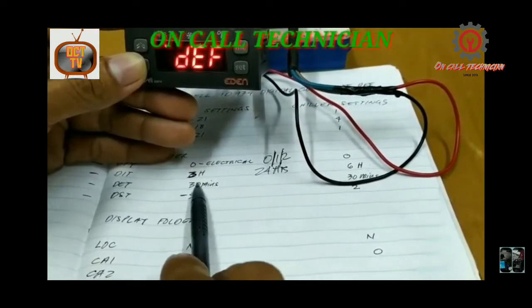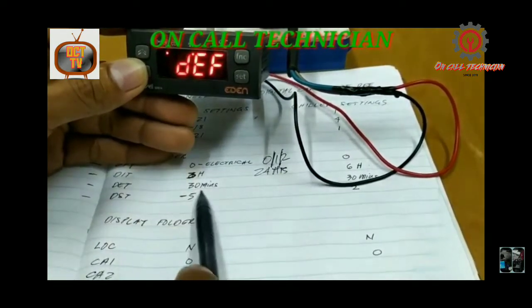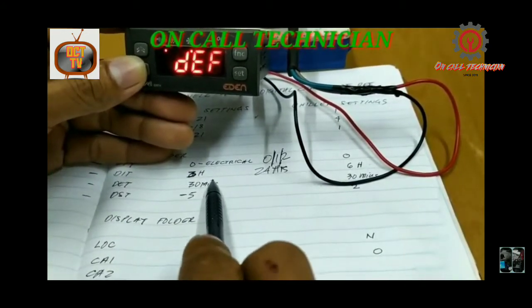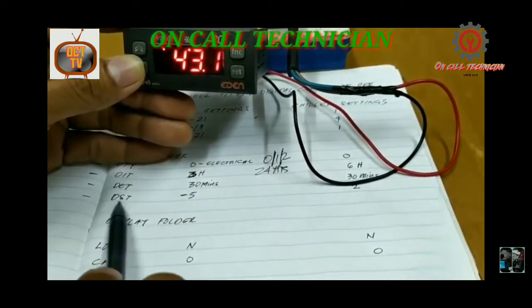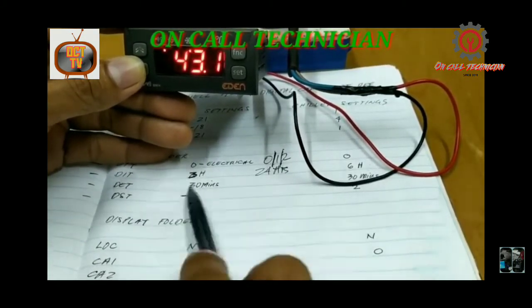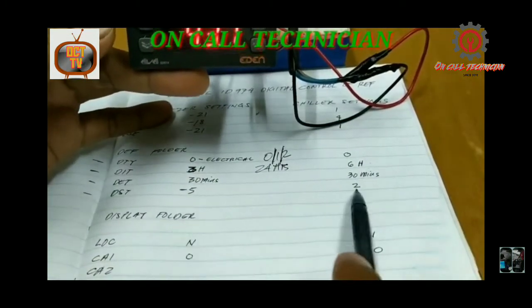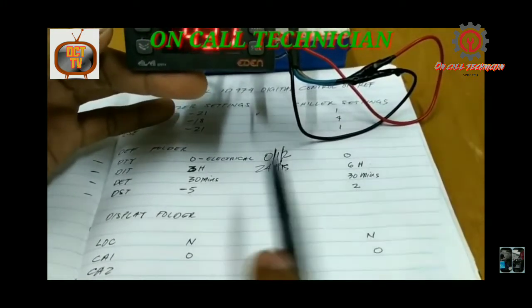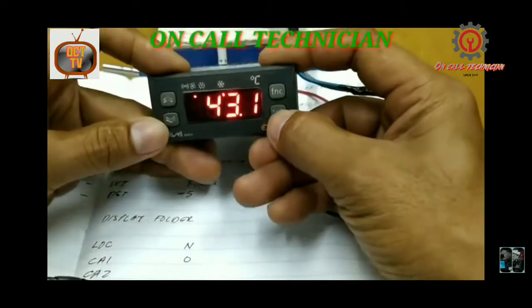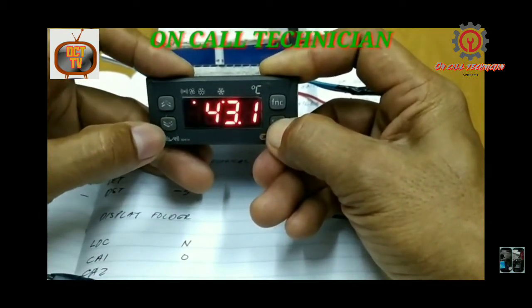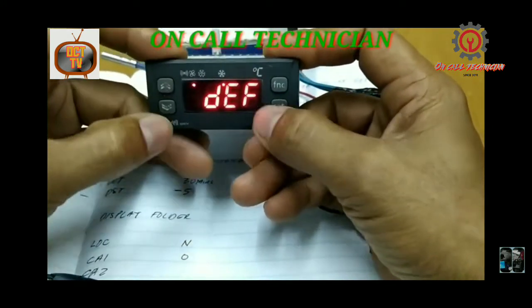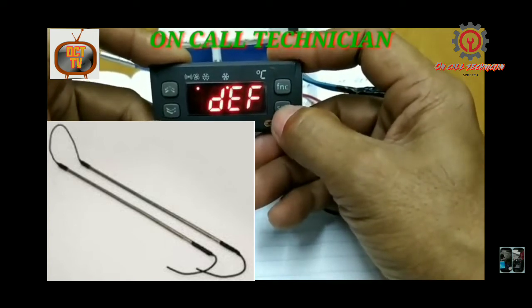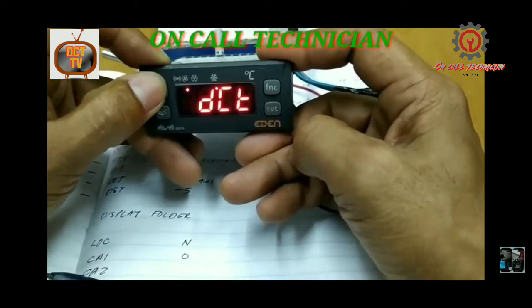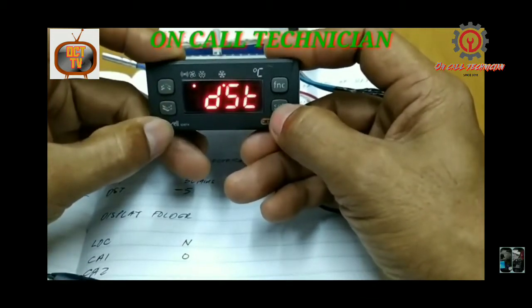So do not, okay, I'm warning you, do not disable the T2 on the E2 in Eliwell sensor. Okay, so in chiller, just set it to 2 degrees Celsius, and that's ideal. Okay, so just in case we have frost formation in our evaporator, so this is the purpose of defrost. Okay, but in chiller, it is not necessary to install a defrost heater. Okay, guys, once again, let's change the DST, which is -5 in freezer setting.